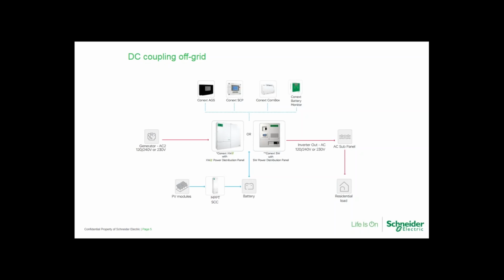Under conditions where the PV cannot keep up with the load demand, the batteries may discharge to low battery cutout unless a backup generator is installed, in which case the XW automatic generator start is highly recommended. And I should mention that it is really risky to design off-grid without a backup generator. I think recently of installers that have done this, and really the only way that is feasible is to have enough PV and enough storage to get you through the worst case scenarios.